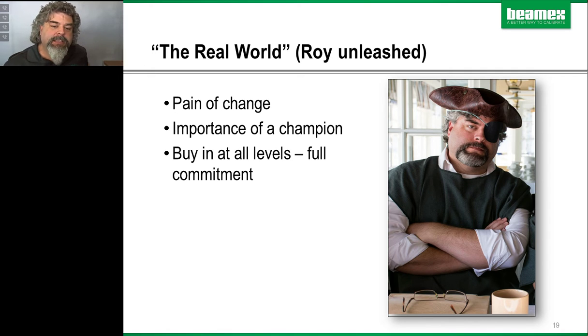And one thing that I want to point out here is that there might be some trepidation. You don't want to be the guy that says, all right, our program is a D, or it's an F, or it's a C, but it's actually really bad. It really is an F, but I don't want to say it out loud. So one thing that's pretty common is that at the customer sites that I go to, every different customer that actually performs a calibration, it doesn't matter what country I go to or what continent, it's similar. And if you don't have a good grasp on your calibration program, everybody thinks they're the only one that is struggling. And if you're struggling with your calibration program, it's okay. There's no shame involved with that as long as you are able to move forward.